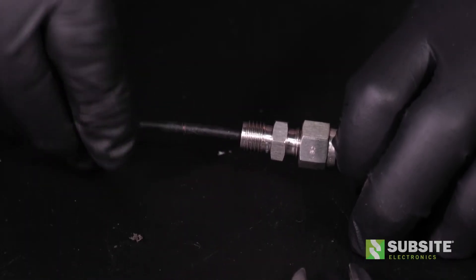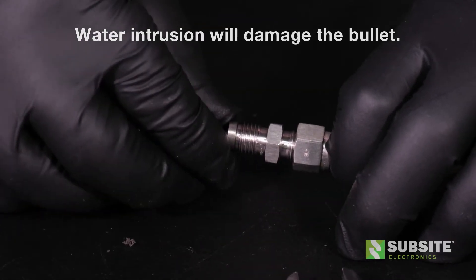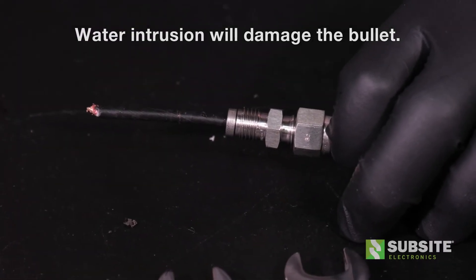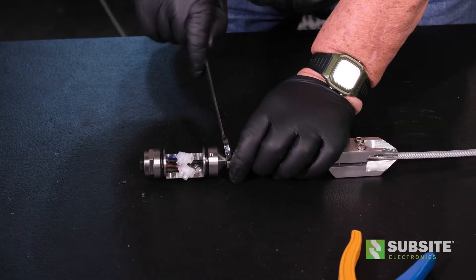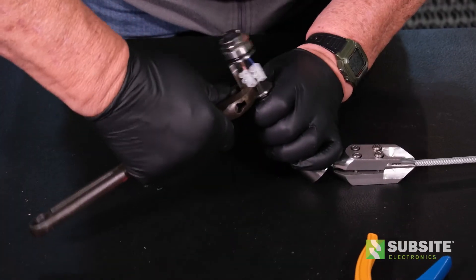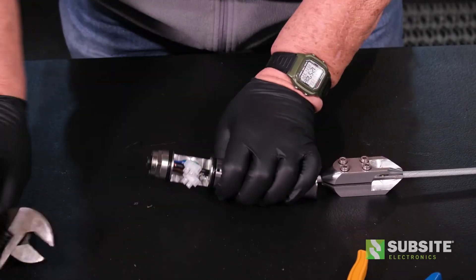To avoid water intrusion, install the washer and O-rings to the end of the cable. Reassemble the bullet and the ferrule body. Use a 1/2 inch wrench to hold the ferrule body while fully tightening the bullet using the adjustable wrench.